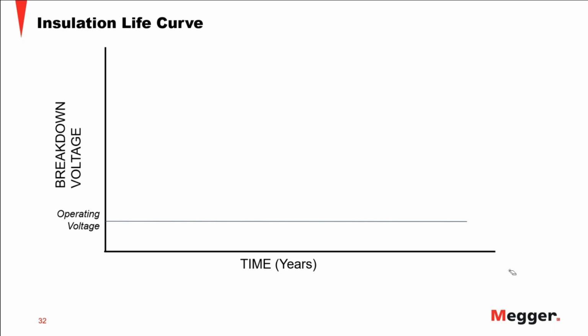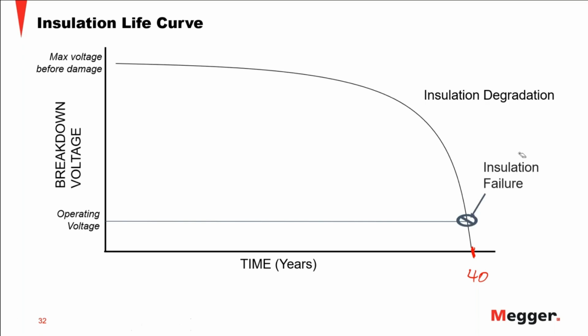A little bit more about insulation. You could have an insulation with an expected life of 40 years, let's say, and that is under the condition that you're always operating at the nominal voltage. Now, as the insulation ages, the insulating capacity reduces. So the typical life curve of an insulation is this. At the early stages of the insulation, you have a lot of insulating capacity. But as the insulation ages, it's going to reach a point where even the nominal voltage is going to break down that insulation, and you're going to have a failure.